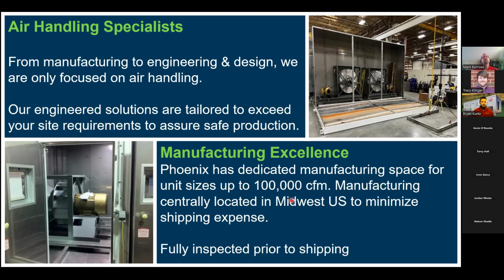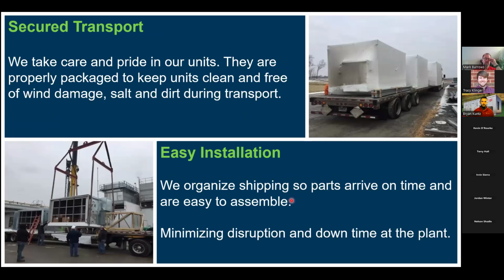Then our manufacturing excellence, kind of talking about the white glove approach. Mark mentioned fully inspected and tested prior to shipping, and then retested once they're installed on site. So we want to make sure that our units leave the facility and show up on site just like they left our facility, right? So we make sure we shrink wrap all of our units and secure them during transport. And make sure that we minimize any disruption and downtime at the plant. So we want to have easy installation. You can see, there's a crane here lifting up each section of the unit, typically in order. I've seen these get installed within half a day, a single unit, for example. So they can be fairly quick depending on who's doing the install.